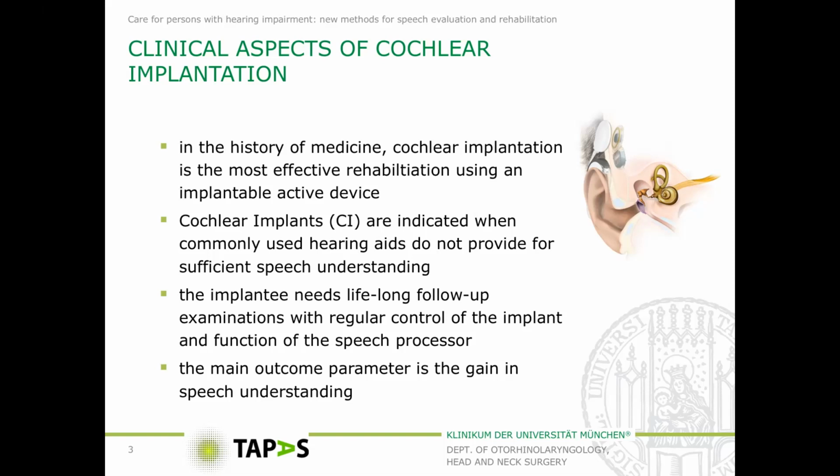But then the implantee needs a lifelong follow-up. You have an implant inside your head, and of course you need to test for the function. And there are some updates, of course, for the speech processor you have on the outside of the head, and the implant itself stays for years or decades. The first implantee of the Munich clinic was implanted 39 years ago. So it's still inside and it's still working. The implant stays, but the outside thing, the speech processor, is changing.